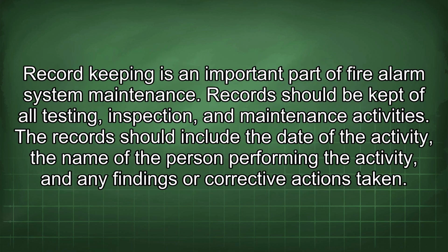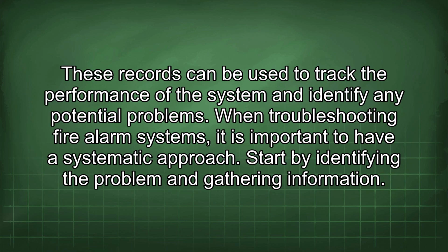Record keeping is an important part of fire alarm system maintenance. Records should be kept of all testing, inspection, and maintenance activities. The record should include the date of the activity, the name of the person performing the activity, and any findings or corrective actions taken. These records can be used to track the performance of the system and identify any potential problems. When troubleshooting fire alarm systems, it is important to have a systematic approach.